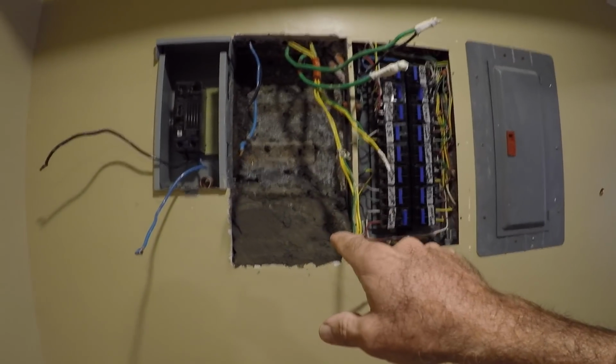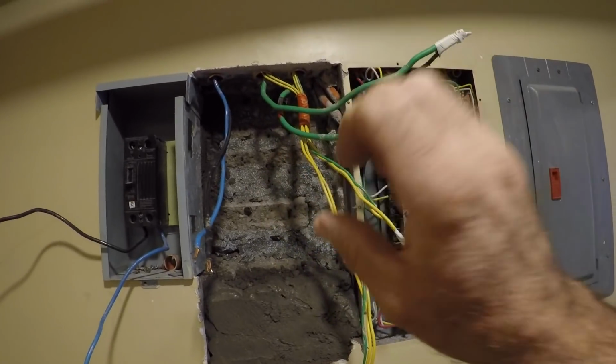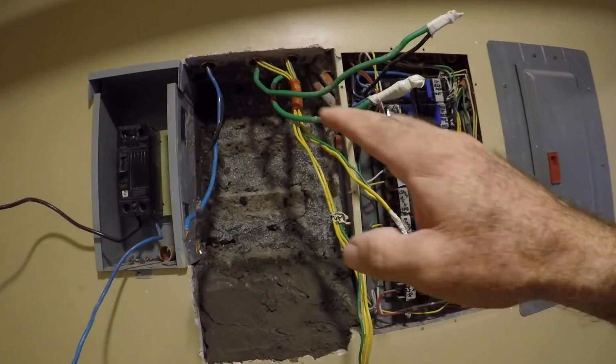It's another power source that you have an option to choose on or off, one or the other, and that's why he put a manual transfer switch on. But once I explained to him, he said, yeah, we'll have to take that out, and he took that out. And we pulled the one up here, since that was a manual transfer switch for either electric or generator, and remember, we're doing the automatic transfer switch, so we removed that as well, and we will do all the wiring for that. Hopefully we get back into that tomorrow, so that we can test the generator.